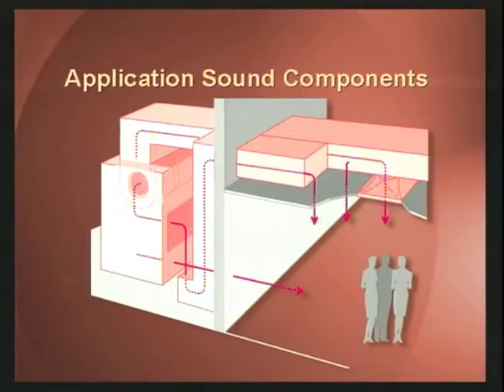If we look at the application that we've seen before, the typical application layout, we see the sound paths again, and specifically I'd like to take a look at how that relates to the source from the product. On the right, we see the sound coming from the discharge duct, whether that's through the diffuser or from duct breakout. Both of those sound paths coming into the room are being driven by the ducted discharge coming from the product. If we look at the wall path coming from the mechanical equipment room into the occupied space, or for that matter, the return path coming into the occupied space, both of them are being driven by the sound component which is the combination of the free inlet and the casing radiated from the product. Not shown in this figure, however, if we had a ducted return situation, the wall path again would be driven by the casing radiated only, and not the casing plus inlet.